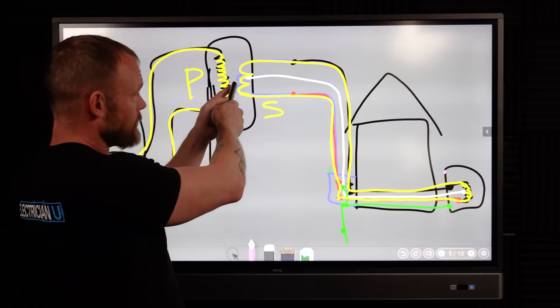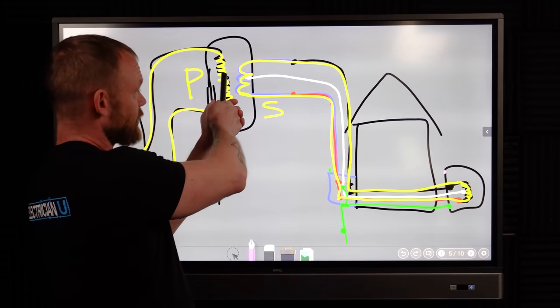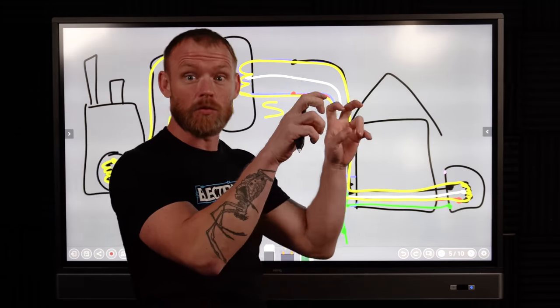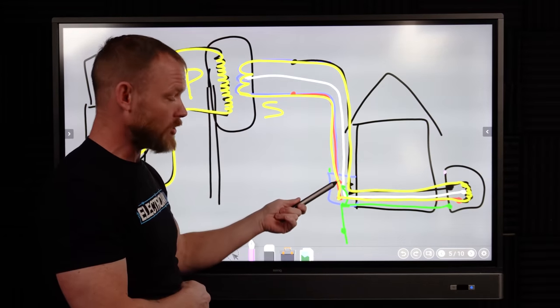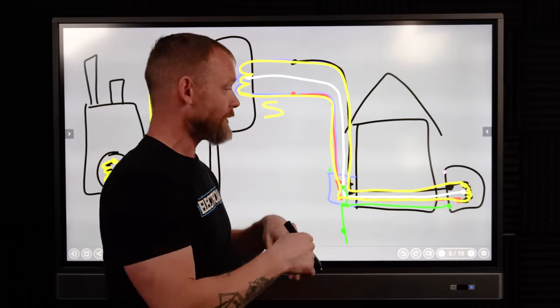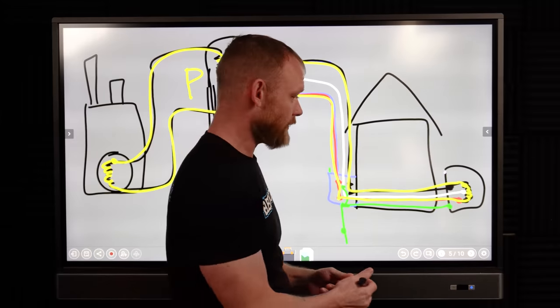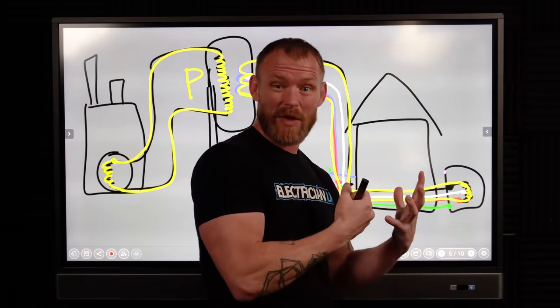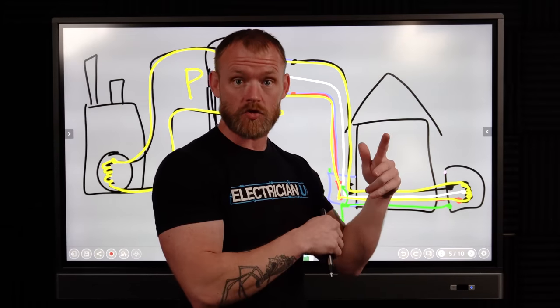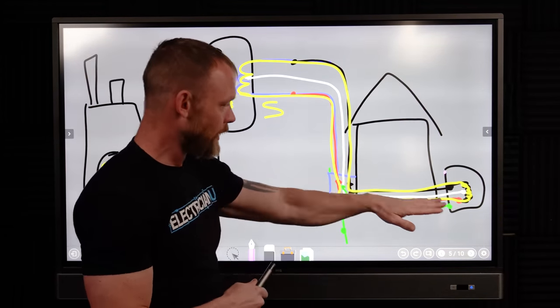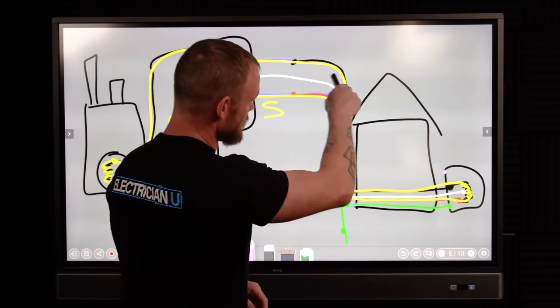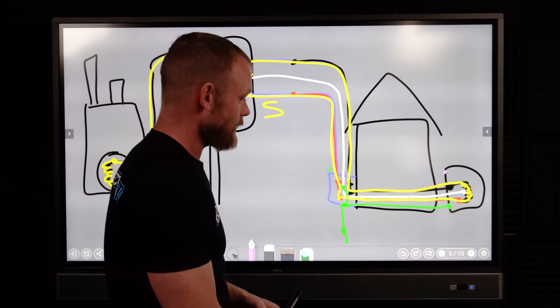We essentially derive a ground by connecting the neutral to a green or bare conductor and bringing it out to the equipment. If there's ever a ground fault — say a conductor lands on the metal casing of a piece of equipment — there is a path back to neutral that will allow that breaker to trip. We run an equipment ground for protection. The primary side can influence the secondary side and vice versa.